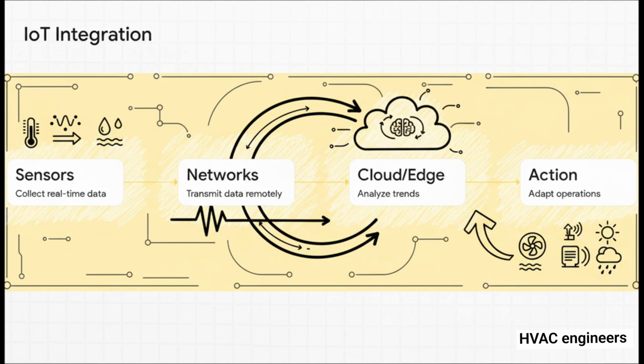Step 1: smart sensors constantly collect real-time data—temperature, vibration, water flow, the whole shebang. Step 2: communication networks instantly beam this data away from the site. Step 3: cloud or edge computing analyzes the data for historical trends. Step 4: the system takes automated action, adjusting fan speeds, tweaking pump output, and adapting to the daily weather, all without a single human stepping foot on site. It enables true predictive maintenance.